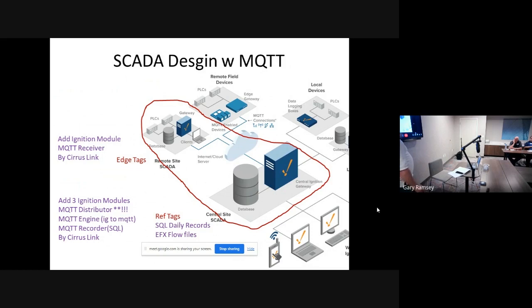But if you lose connectivity, are you caching them? MQTT has its own store and forward mechanism, which is a little different than Ignition. I didn't know if you were caching it or just relying on MQTT to cache and save. If you don't use MQTT, Ignition has its own store and forward, but we threw that out and said we're going to MQTT. We use their store and forward instead, and you can put it in RAM or on disk. The trade-off being, if the power goes off and it's in RAM, it's gone in that case. We tested that quite a few times because it's important to us.